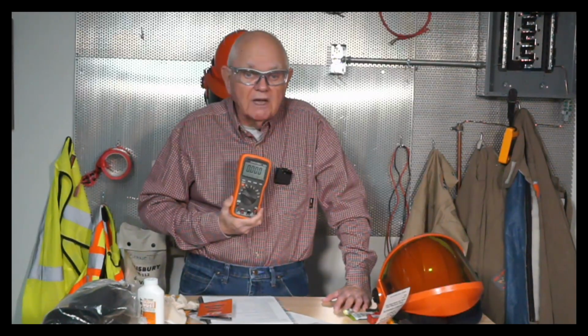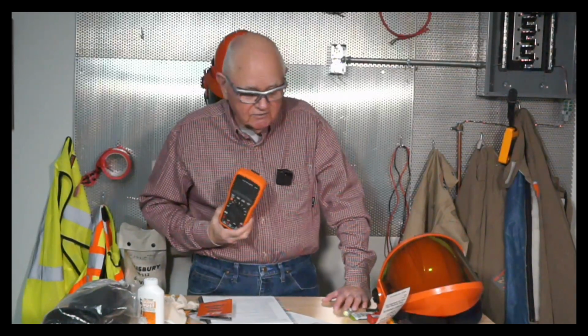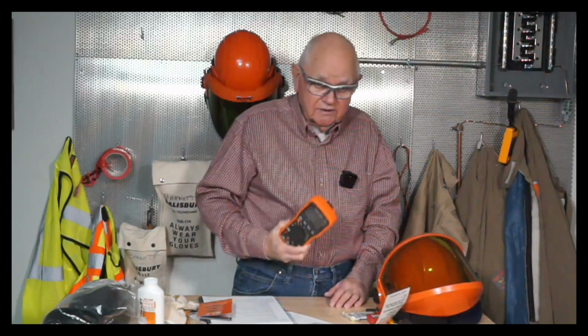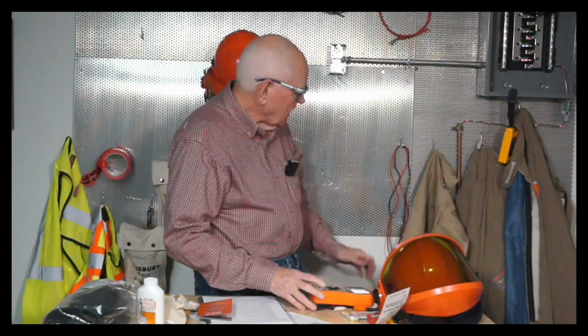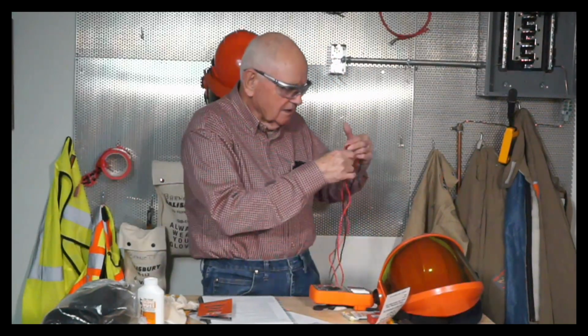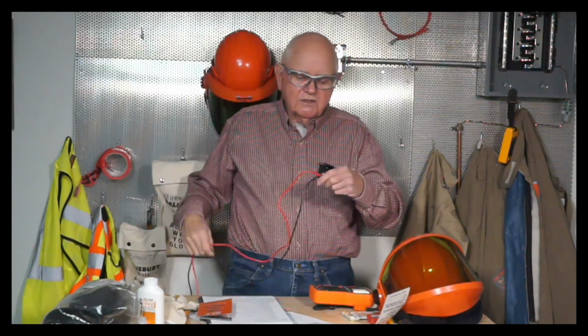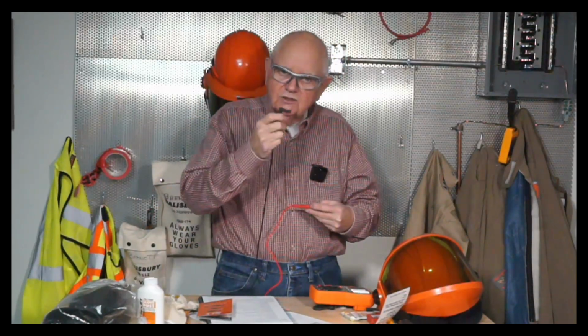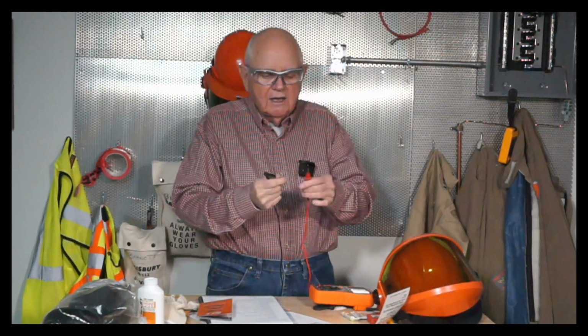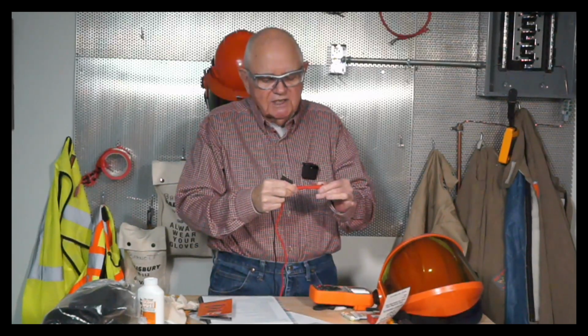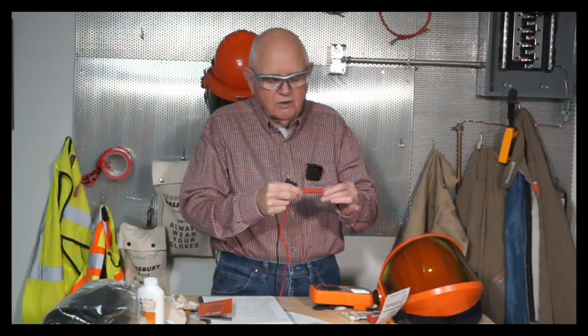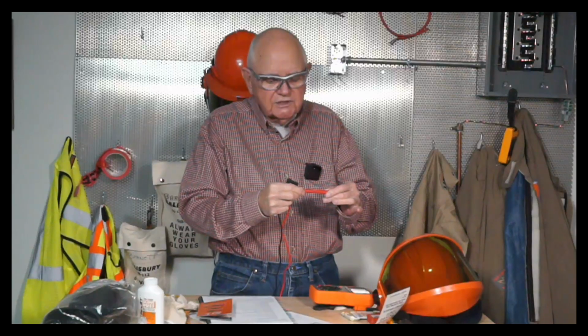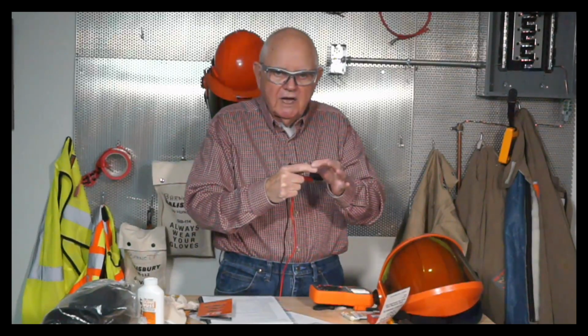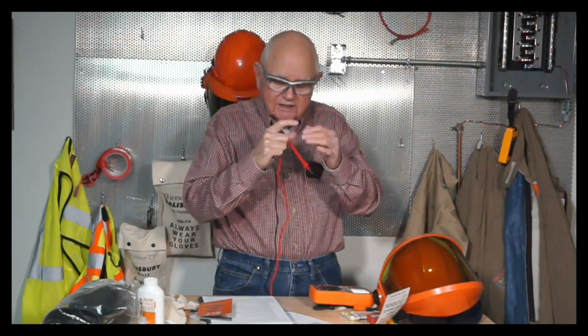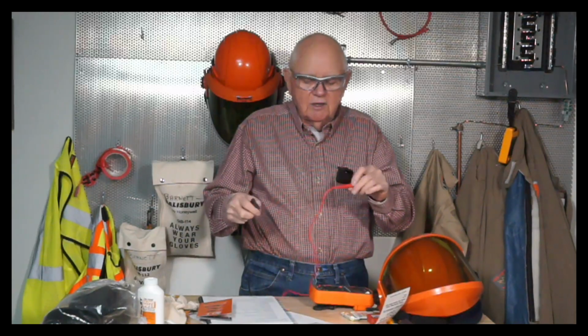So I could certainly use this in my plant for working on up to my 600 volt systems indoors and outdoors. And I'm certainly not going to use it up at 1000 volts and over that. I also want to inspect my test leads. So make sure you do a good physical inspection of your test leads. Make sure they've got shrouds on the end of them. Take a look at the tips. Make sure that your test leads are rated. These are Category 3, 1000 volts, Cat 4, 600 volts. They have a double little box on them, meaning one box inside of the other one. That tells me that they are double insulated.